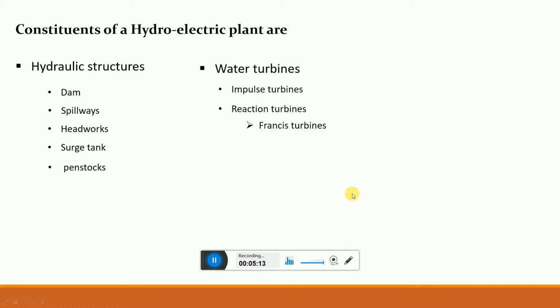So coming to Francis turbines, a Francis turbine is used for low to medium heads. It consists of an outer ring of stationary guide blades fixed to the turbine casing and an inner ring of rotating blades, right? So from the runner, the guide blades control the flow of water to the turbine.